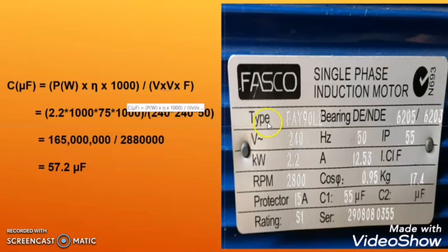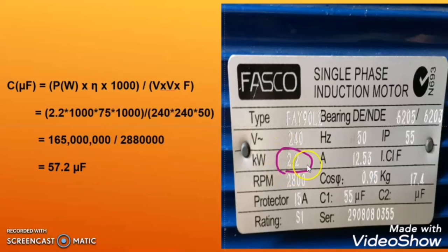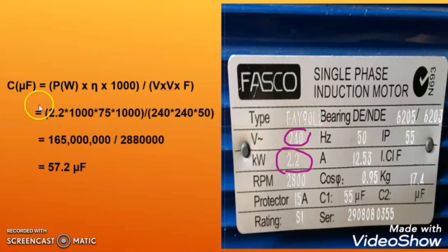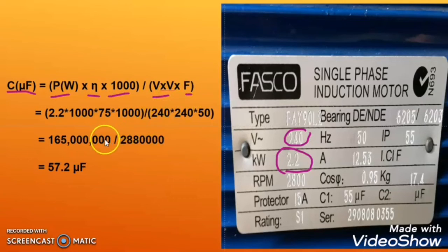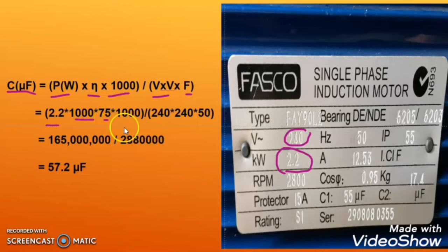Now let us calculate the capacitor rating for a bigger motor. Here the motor rating is given as 2.2 kilowatt and the voltage is mentioned as 240 volts. Using the same formula — C = P × efficiency × 1000 ÷ (V² × f) — the power is 2.2 kilowatt, which is 2200 watts.